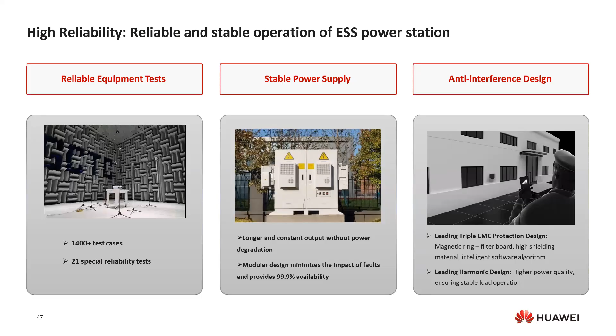Yes, talk about high reliability. In a conventional system, if there is any fault in any of the battery packs, then the whole cluster cannot be used. But in the case of Huawei's Intelligent Smart String energy storage system, the modular design reduces the impact, and only the faulty pack is isolated, and the rest of the system keeps working fine.